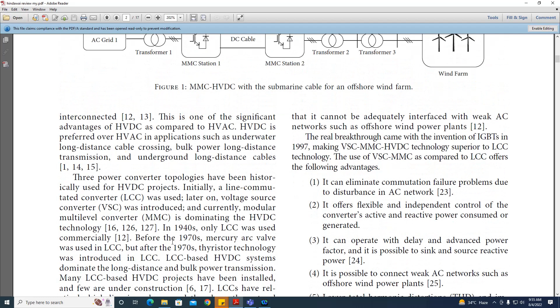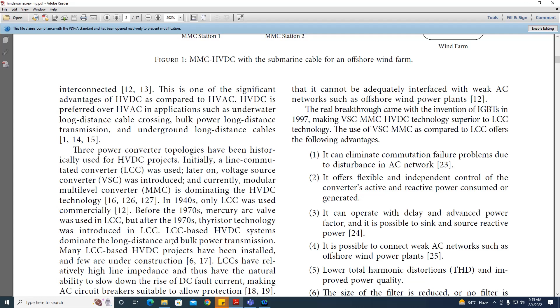So without reversing the voltage polarity, power flow direction can be changed in case of VSC, but it's not possible in LCC. LCC can conduct current in only one direction while blocking voltage in both polarities. Moreover, the LCC type converter has short circuit ratio of more than 2, which means that it cannot be adequately interfaced with weak AC networks such as offshore wind power plants. Yeah, this is true. Offshore wind power plants cannot be integrated in an LCC, but weak grids such as offshore power plants can be integrated in VSC based or MMC based converter stations.